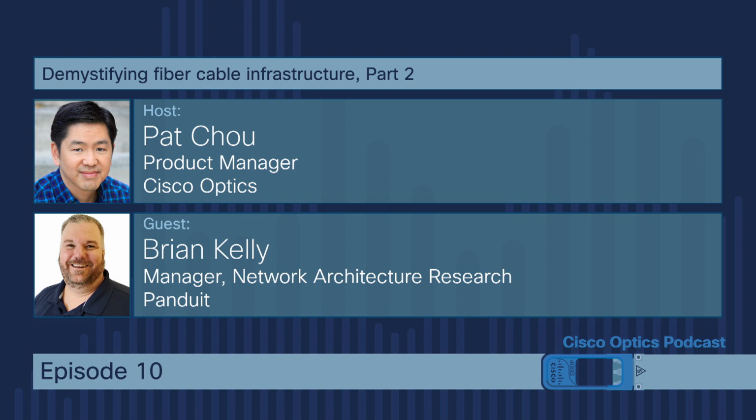One other thing about the DAC, the direct attached copper, I've heard is that the copper cable itself, the twinax cable, is much, much thicker and rigid. Yeah, it's much bulkier than fiber, especially at higher speeds. Is that a consideration you see in the field? Absolutely. The direct attach copper cables, especially at 100 and 400, are heavy gauge, and it's a two-factor issue. One, it's rigid to run and cable manage. And two, there's a weight factor to it.